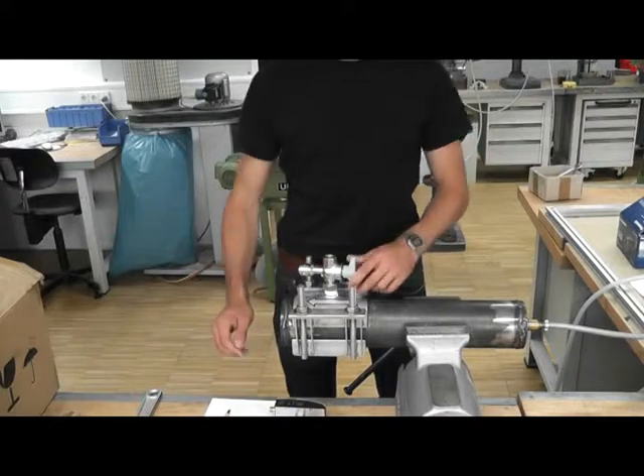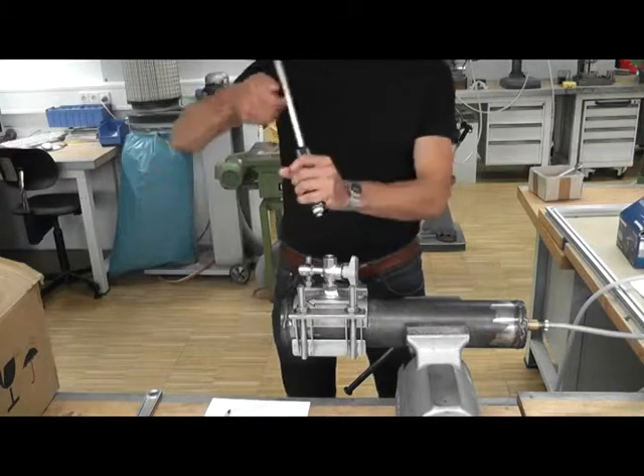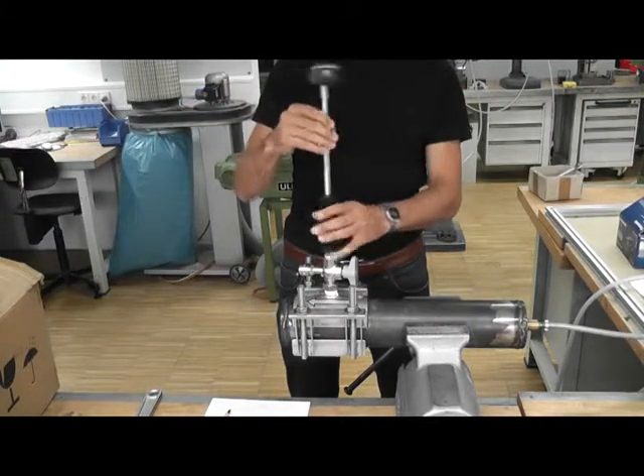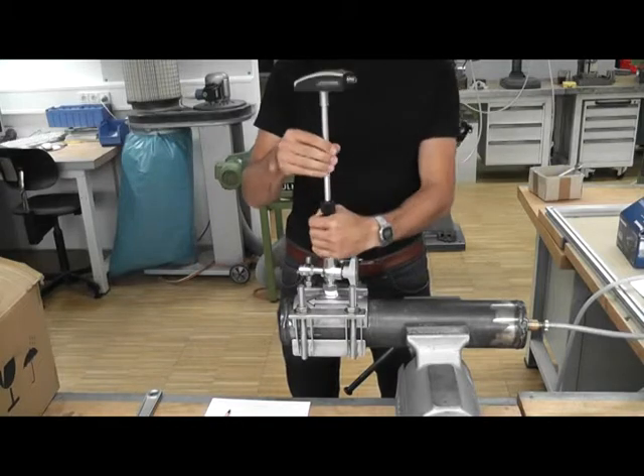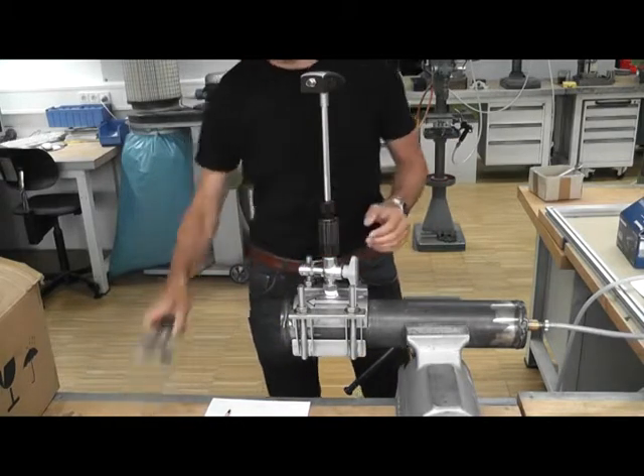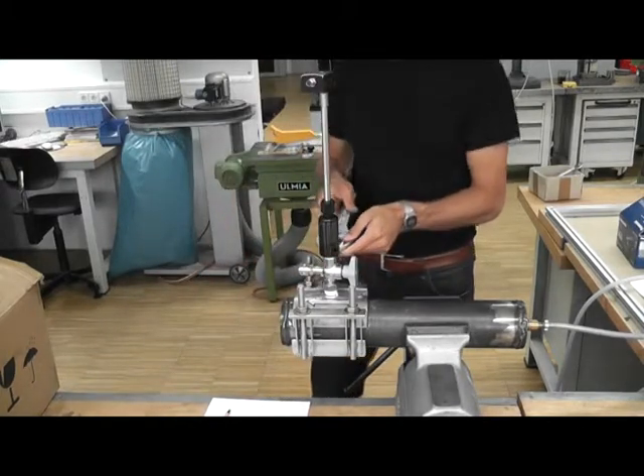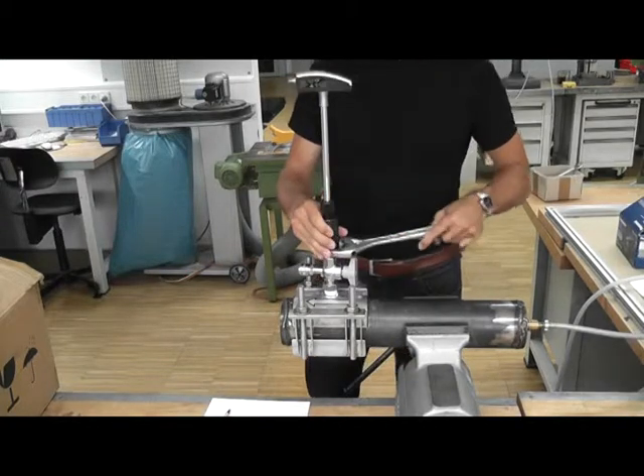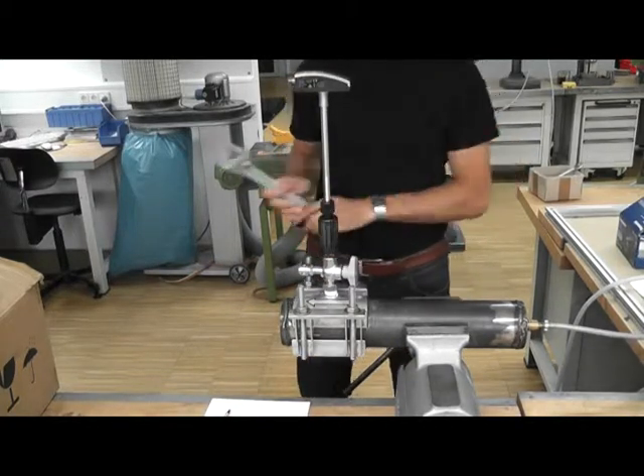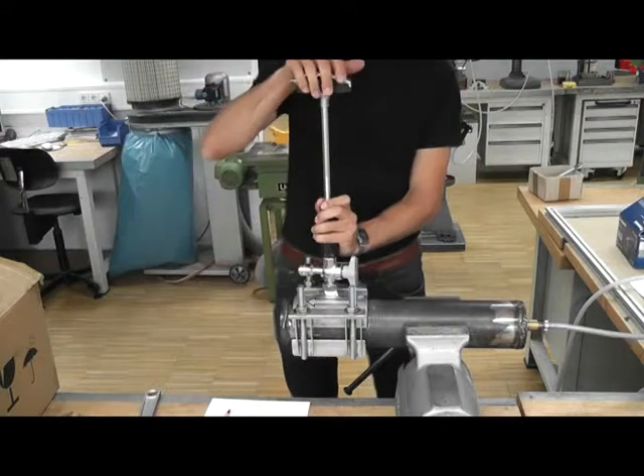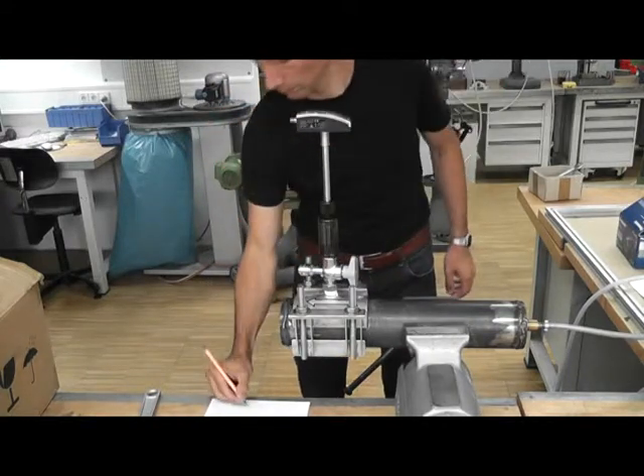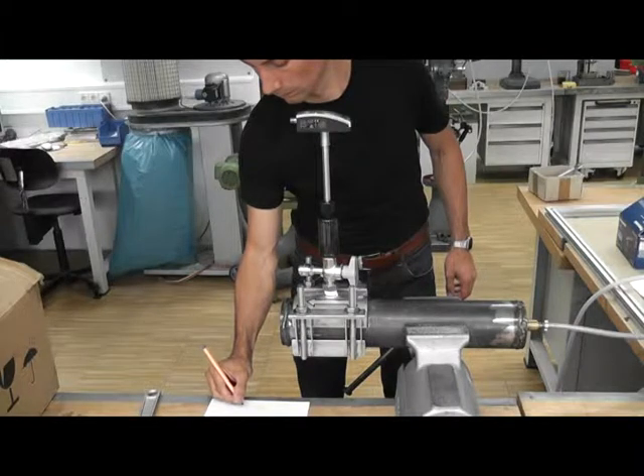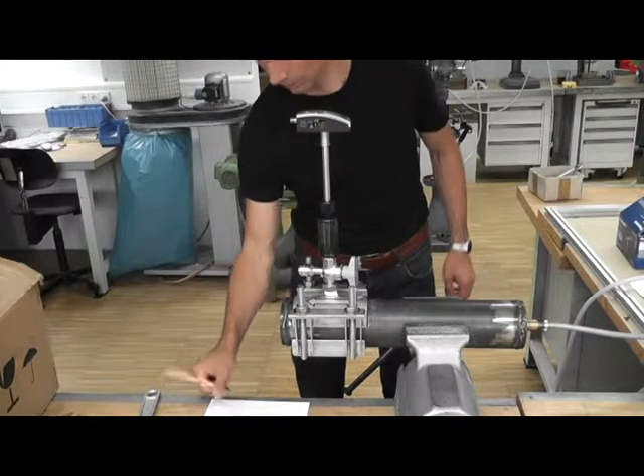To do that, you have to make a few steps. First, make sure the ball valve is opened. Second, screw the transmitter on the ball valve and tighten it with a wrench. Third, press the transmitter to the end limit. Fourth, read and notate the value on the scale.